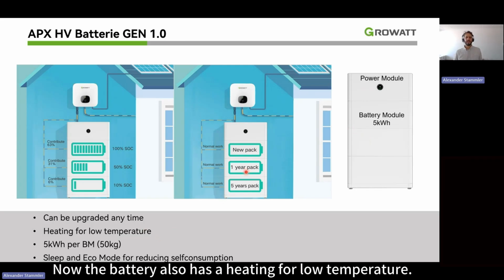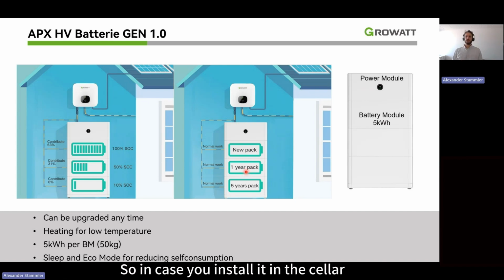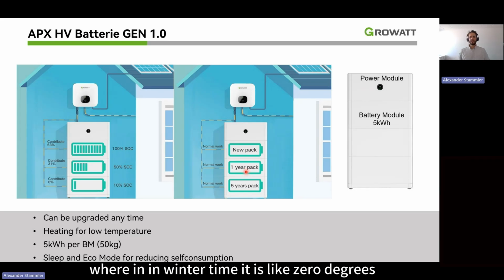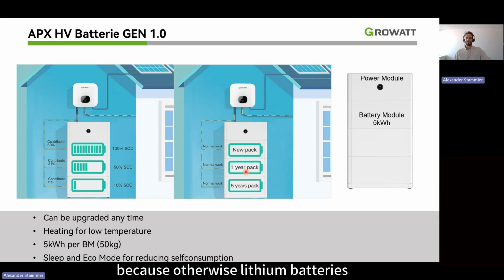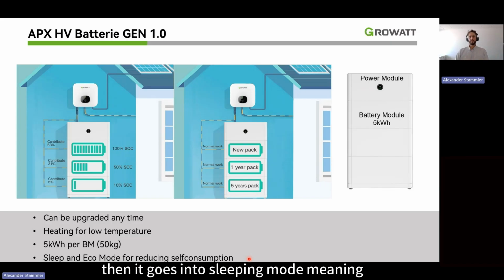The battery also has a heating for low temperature. So in case you install it in the cellar where in winter time it is like 0 degrees, it uses part of the PV energy to heat up, because otherwise lithium batteries are not able to charge very well. So this problem is circumvented by heating, similar as in a car. Then it also has a sleep and an eco mode. When the battery, for example, is empty and the system sees there's no PV coming in, so there's no chance that it can be charged, then it goes into sleeping mode, meaning it will reduce the self-consumption energy. Because of course, if the battery is on, it will use up some power.